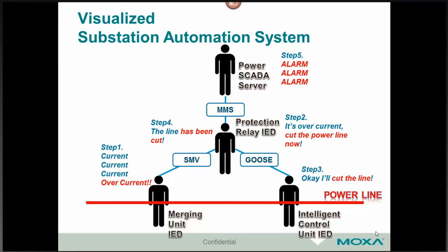And the same thing with GOOSE. The GOOSE messages are between a control unit or any other IED and the protection relay, just letting them know what's been done, what event has occurred. And then everything that does happen that you want to represent on a SCADA somehow, that's done via the MMS protocol, which is very similar to almost like an SNMP from the IT side of things, but MMS gives you the status of things going on in the substation.